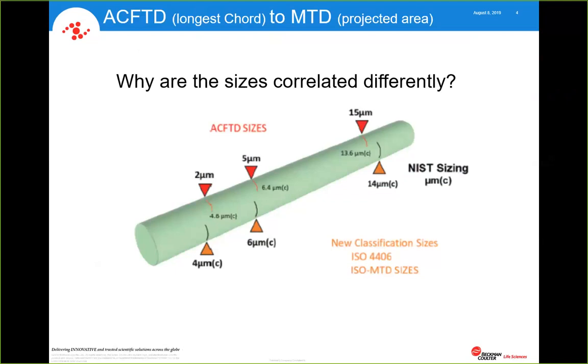Even though it's calibrated with MTD, we can correlate the channel sizes, MTD sizes, to the ACFTD sizes of old, and gives you the NavAir standard in the software. So basically, you can still report out the NavAir standard with an MTD calibration and look at your empirical data versus your new data. And so knowing that we have two different sizing methodologies for the calibration.